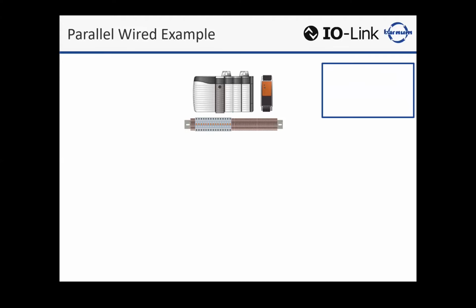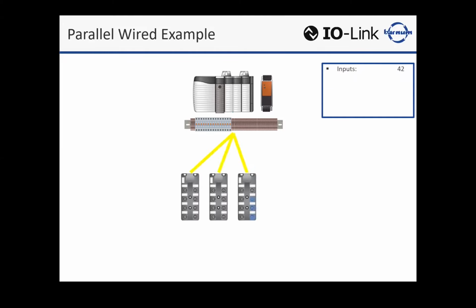All right, so let's just go ahead and make up a layout. What do you want to start with? Well, let's just go with a small to mid-sized machine. Let's say 42 sensor inputs. Perfect. So to do that, let's maybe wire them to some field blocks. Yeah, even if you're using direct wiring, most people at least have migrated to an IP67 style quick disconnect IO block. So in this case, we need 3 8-port blocks, which are capable of 2 signals apiece, total of 48 input signals. We have 42. So yep, those 3 blocks suffice our needs. Perfect. And that leaves us with 6 spares.